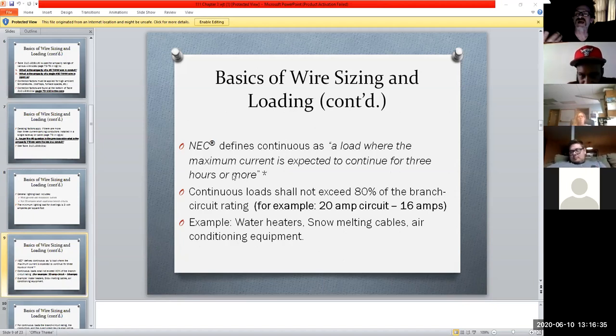So where do you expect to actually see something running for 3 hours or more? Well, that's the big boys, usually like your AC and your furnace, that kind of thing. Those things are going to be running constantly in summer and winter conditions, right? So this would be how we would multiply something like that out. We would say, okay, continuous load shall not exceed 80% of the branch circuit rating. So we would have to actually do a little math and see how I size my circuit breaker for that. And it's special equipment usually, right?